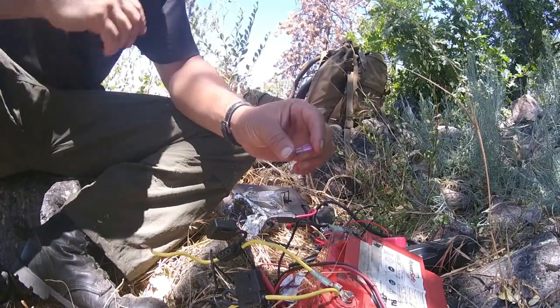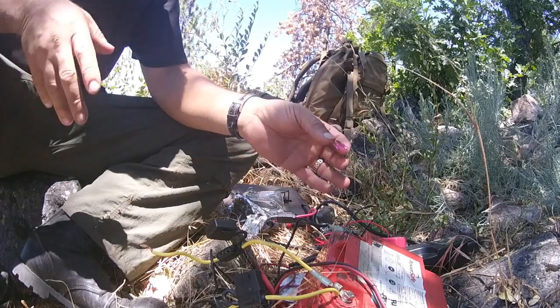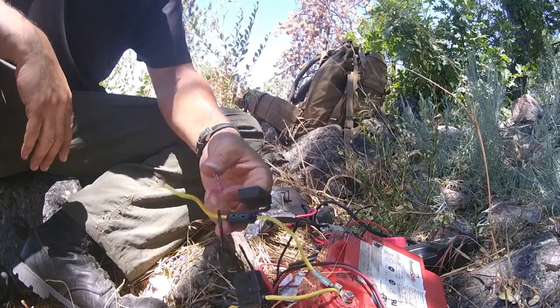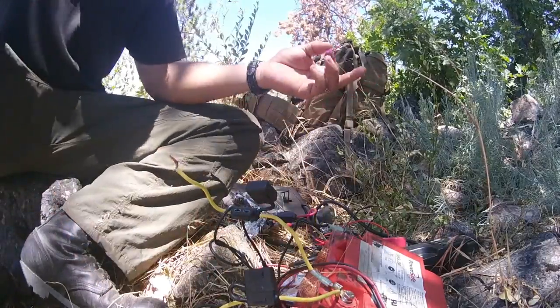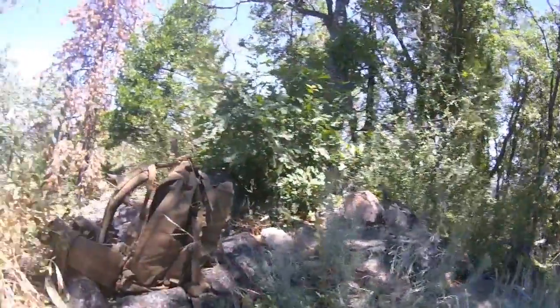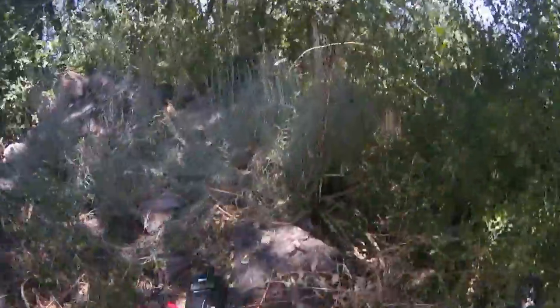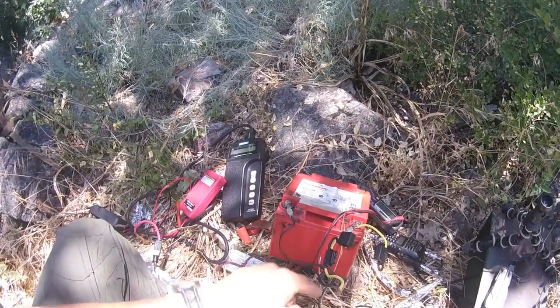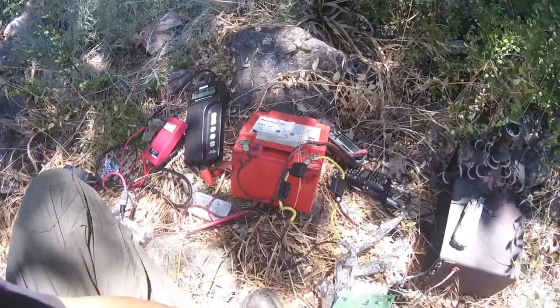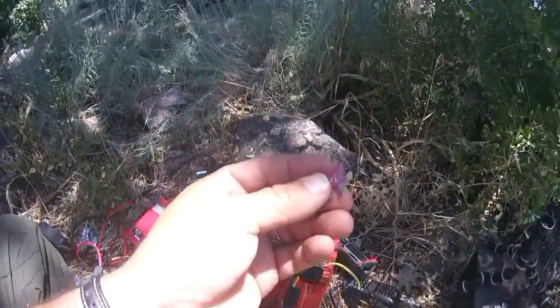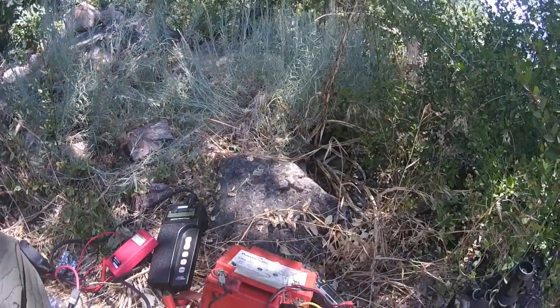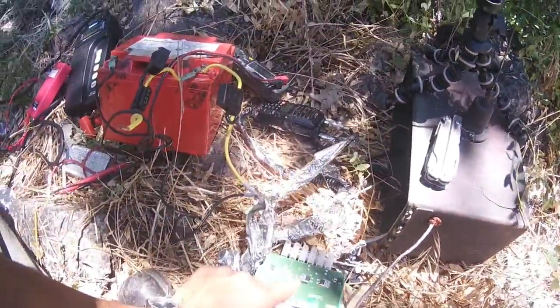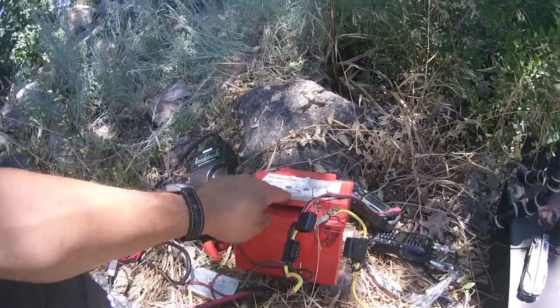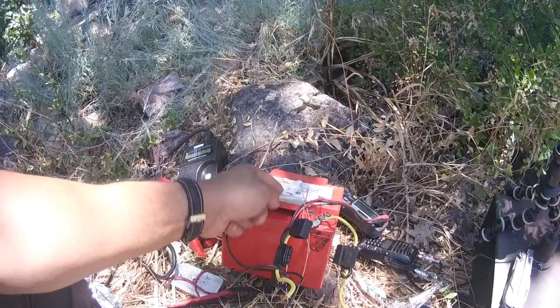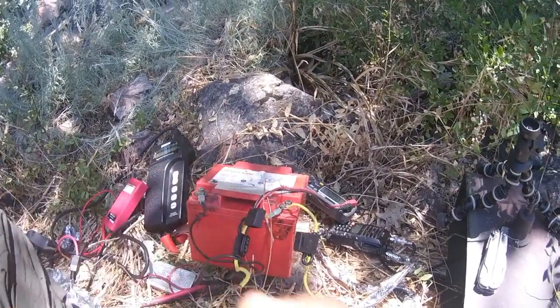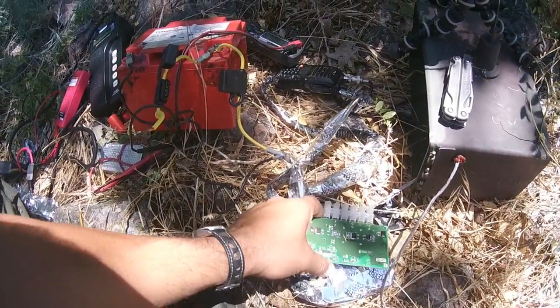Let's say this was an amateur, garage build, which it is, but you didn't think about fusing the hell out of your equipment, especially out here in a wooded area where it's tinder dry. Let's say I didn't fuse this thing at all. There was a short, meaning maximum current going from the battery into this device. If that short was not protected by a fuse, the components here could have heated up because it's getting a lot of current from the battery, and this battery produces a lot of current. I would say 30 amps at a shot.